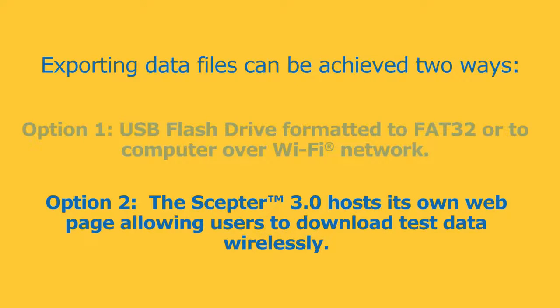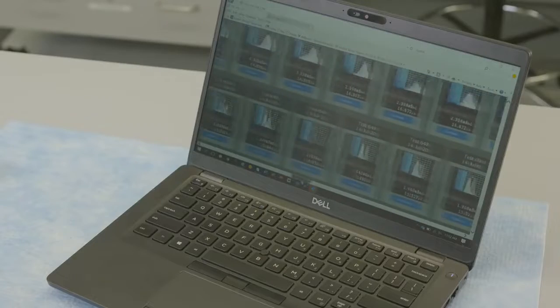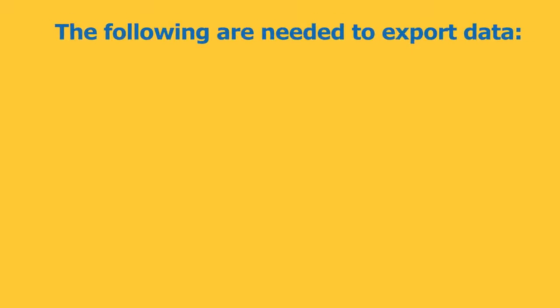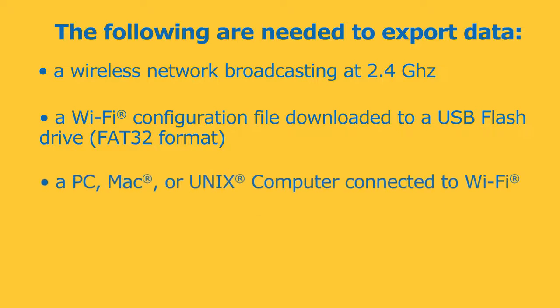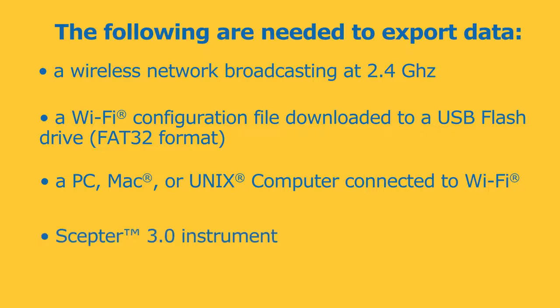Option two: the Scepter 3.0 hosts its own web page allowing users to download test data wirelessly. To export data, a wireless network broadcasting at 2.4 gigahertz, a Wi-Fi configuration file downloaded to a USB flash drive, a PC, Mac or Unix computer connected to a Wi-Fi network, and the Scepter 3.0 instrument are needed.